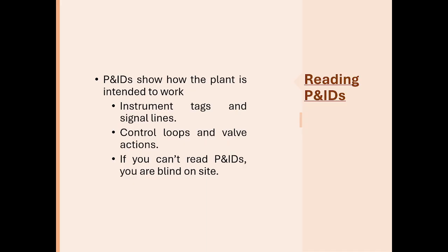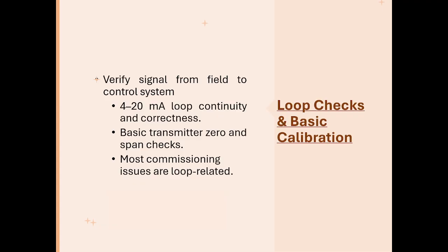So when a problem occurs on site, engineers do not guess. They go back to the P&ID to understand what should be happening versus what is actually happening. So if you cannot read a P&ID, you are effectively blind on site, no matter how good your PLC skills are. Once equipment is installed according to the drawings, the next step is to confirm that signals are working correctly. And that takes us to the next slide, which is the loop check and basic calibration.